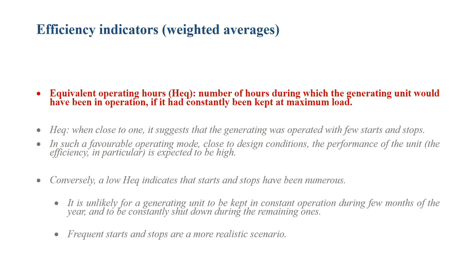Now, the equivalent operating hours is a good indicator, but does not provide all the information we need. When it is high, we know the unit has been operated for a long time during that year, so starts and stops have been few, because otherwise we couldn't have reached that high number of equivalent hours. On the other hand, when the number of equivalent hours is low, we have no specific indication. Two things are possible: there were few hours at full load or many hours at partial load.